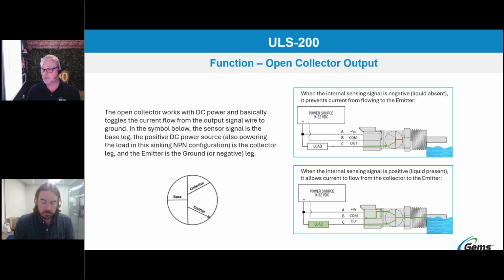When the internal sensing signal is negative, as shown in the diagram in the upper right, that means liquid is absent, and it prevents current from flowing to the emitter. Again, this is in a sinking configuration, a wet sinking configuration. Then, when the internal sensing signal is positive, liquid present, it allows current to flow from the collector to the emitter, giving you your positive, yes-I-see-liquid signal.